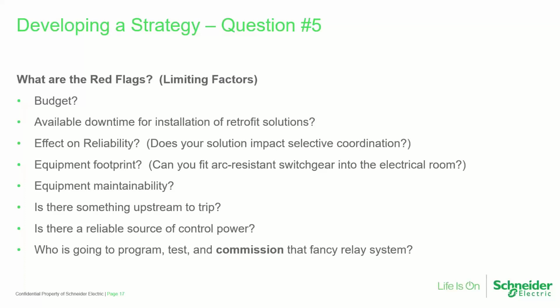Is there a reliable source of control power for that new advanced relay that you want to put in? And then the last one, last but not least, who's going to program, test, and commission the fancy relay system that you want to use? I can tell you stories about, for example, optical arc flash systems where the person that programmed the logic in the relays didn't actually have the optical sensors programmed to trip anything. So instead of providing protection, that relay was providing some degree of a false sense of security. A lot of things have to come together in order to make some of these things work, so just make sure that we're considering these as well.